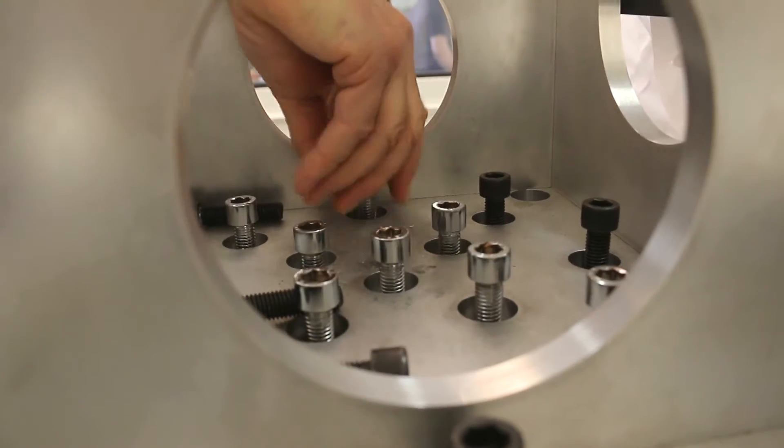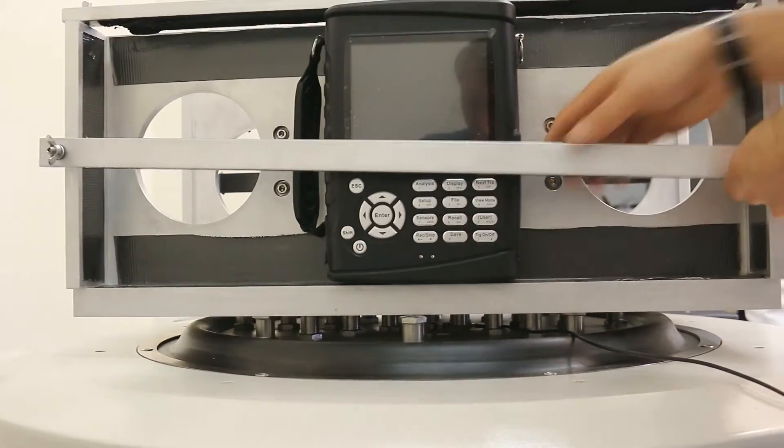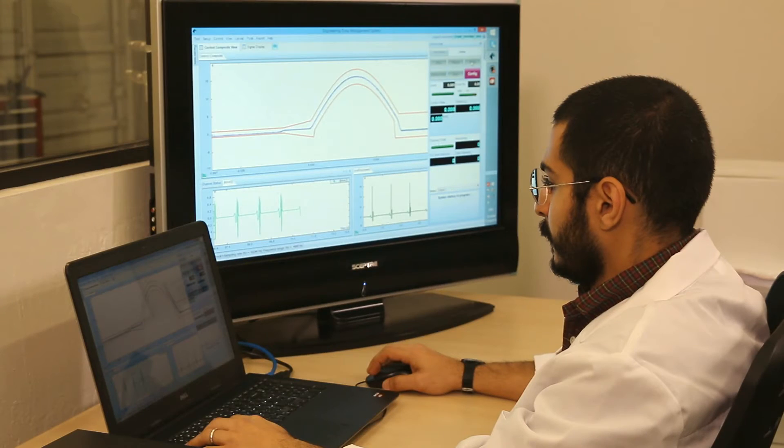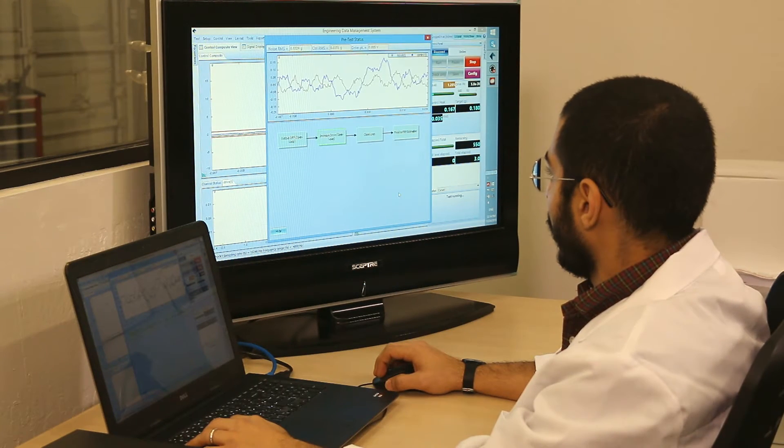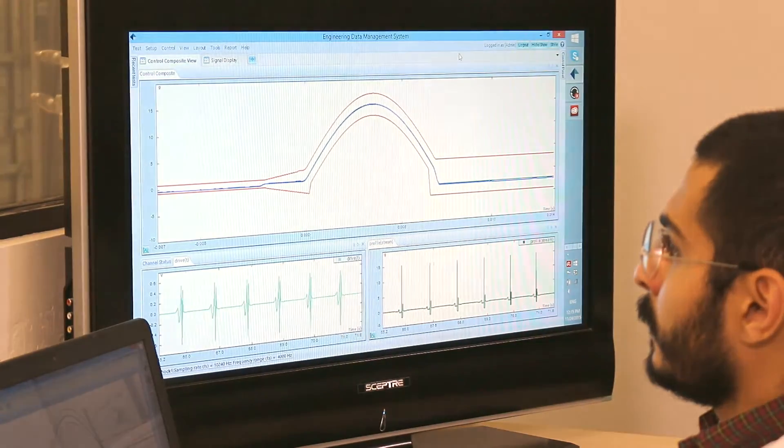Shock tests output a series of pulses to excite the structure under test. Shock tests are controlled using a profile defined in the time domain. Pulse time duration and peak acceleration are generally the two defining characteristics of a shock pulse.